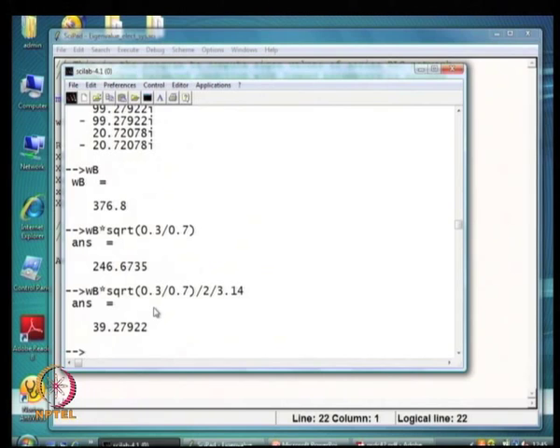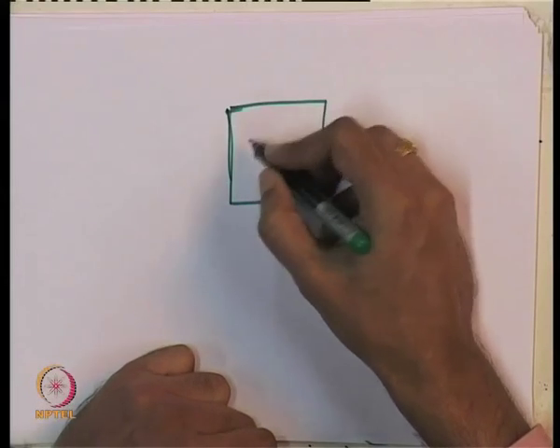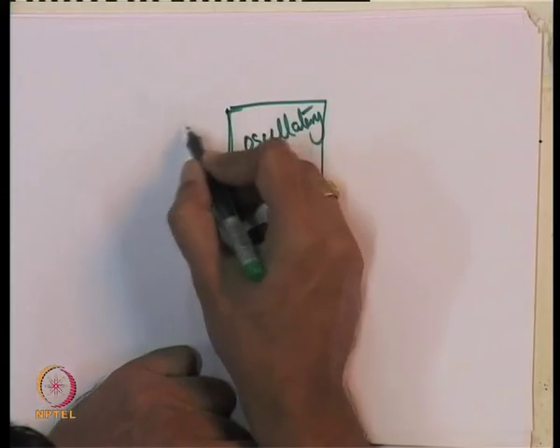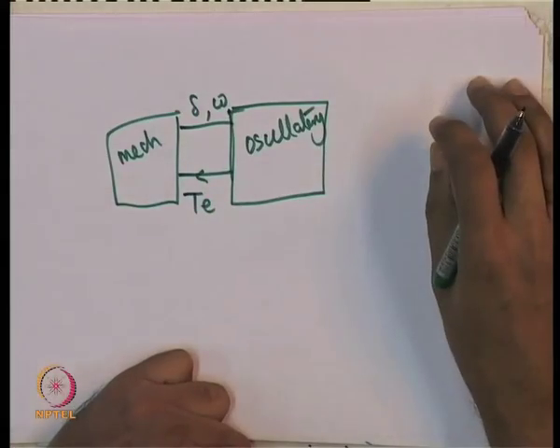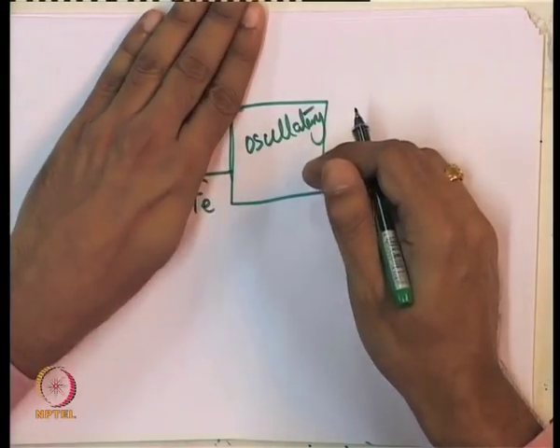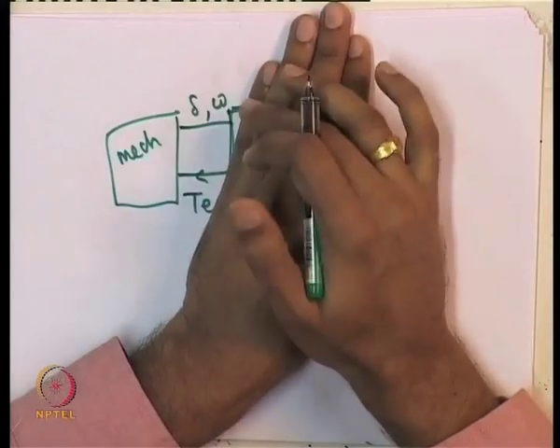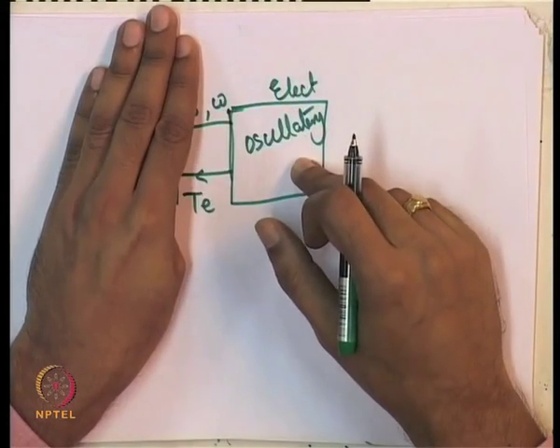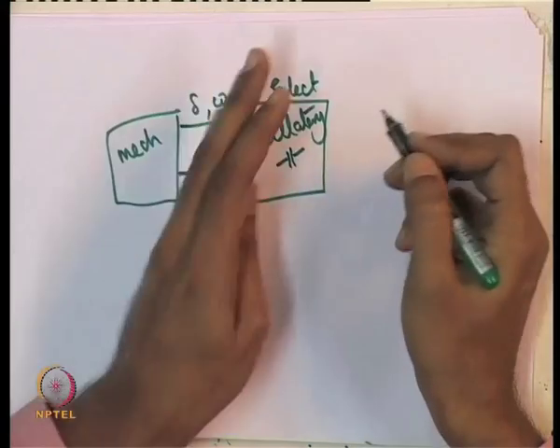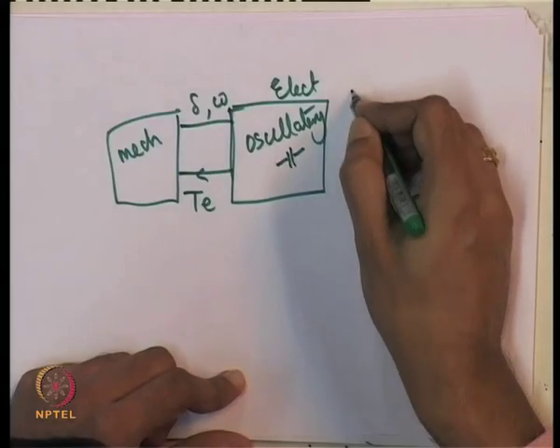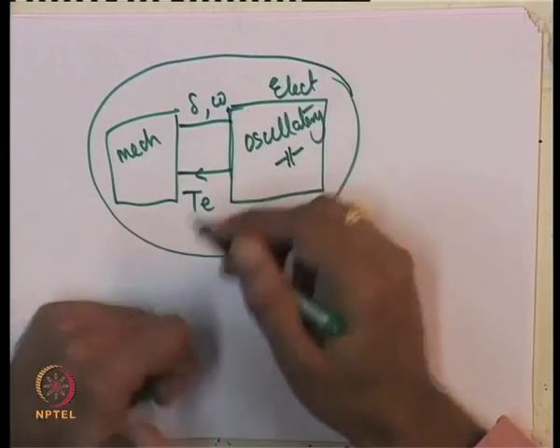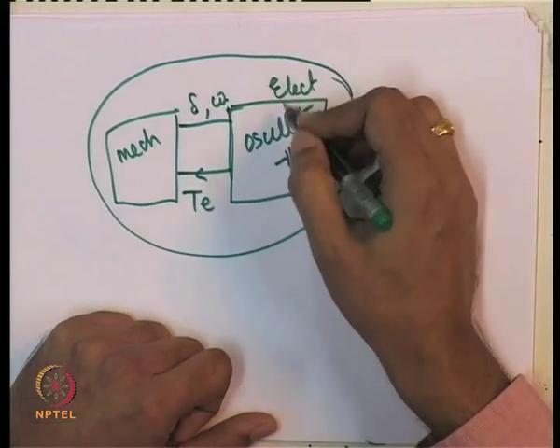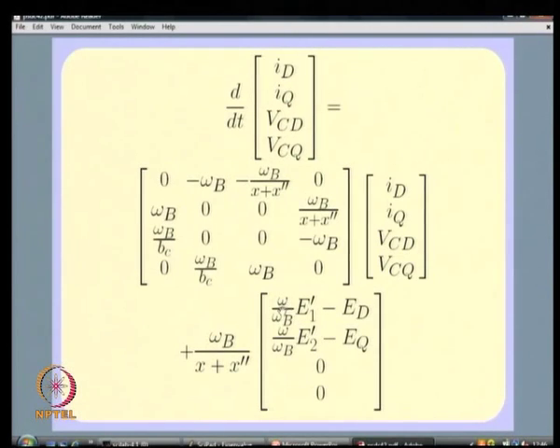The point now is: the electrical network which is series-compensated has oscillatory eigenvalues, and the mechanical system also has an oscillatory response — delta, omega, and T_e interact. When you put them together, it becomes a coupled system. Delta and omega affect the electrical system, and the mechanical system is affected by the electrical torque.